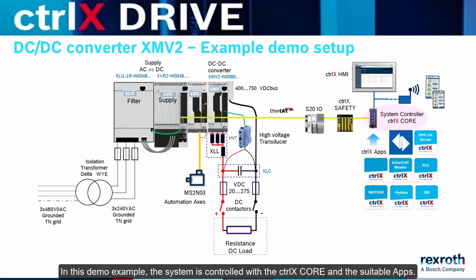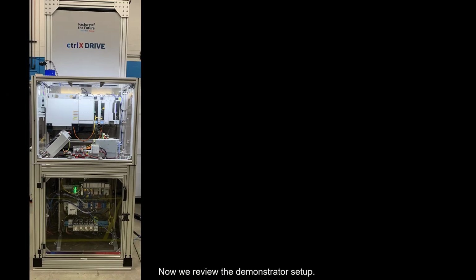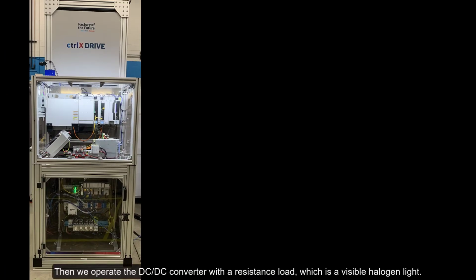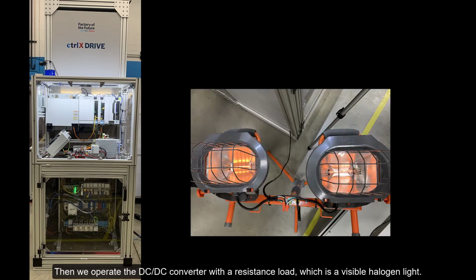In this demo example, the system is controlled with the ctrlX core and the suitable apps. The S20 type IO, the control safety and all ctrlX drive units are controlled with EtherCAT bus. The demonstrator's HMI is web-based. It is created with the app WebIQ and can be displayed with a web browser available in stationary or mobile devices. Now we review the demonstrator setup. Then we operate the DC-DC converter with a resistance load, which is a visible halogen light.